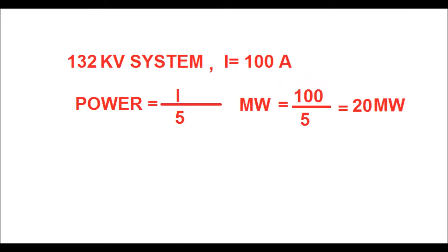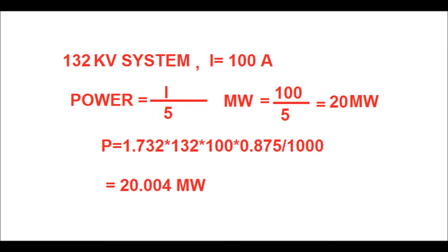For a 132 kV system, if current I = 100 amperes, then to get the power in megawatts you have to divide the current by a factor of 5, giving 100 divided by 5 equal to 20 megawatts. Using the same formula: P = 1.732 × 132 × 100 × 0.875...